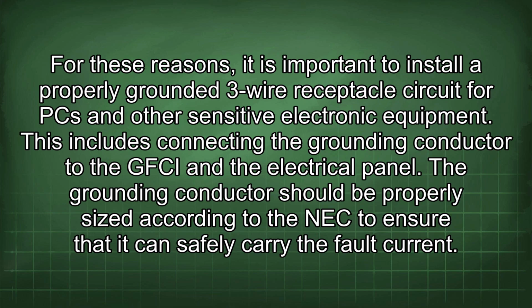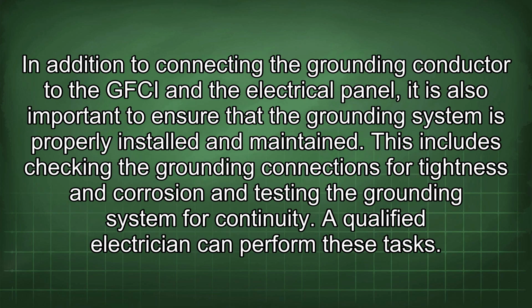For these reasons, it is important to install a properly grounded 3-wire receptacle circuit for PC and other sensitive electronic equipment. This includes connecting the grounding conductor to the GFCI and the electrical panel. The grounding conductor should be properly sized according to the NEC to ensure that it can safely carry the fault current. In addition to connecting the grounding conductor to the GFCI and the electrical panel, it is also important to ensure that the grounding system is properly installed and maintained. This includes checking the grounding connections for tightness and corrosion and testing the grounding system for continuity. A qualified electrician can perform these tasks.